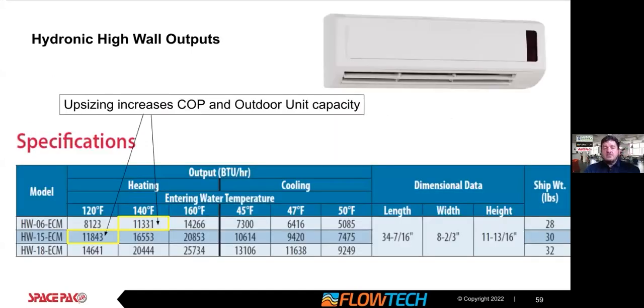I want to make a note on design for these and other units for SpacePak. Flexibility in design is a key thing. I'm showing here that the outdoor unit you choose can change your capacity and your efficiency. If you're going with our small one, the SpacePak 06, it's a smaller unit capacity-wise, and say you had an 11,000 BTU load, or close, that you're trying to satisfy in a room. If you go with the small unit, you're going to need to run 140 degree water. That's not even really an option with our SpacePak because we'll go up to 125. But you can upsize the unit.